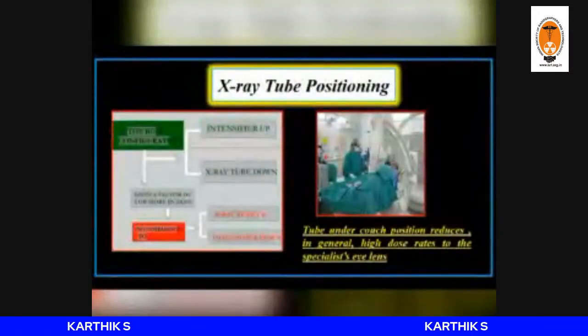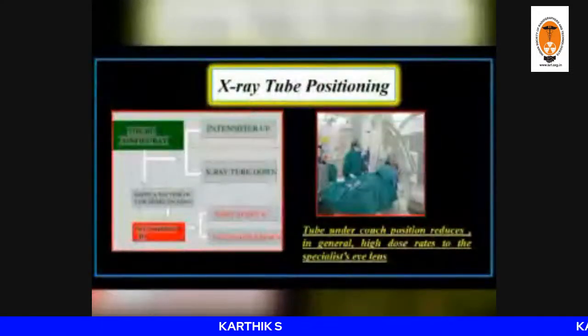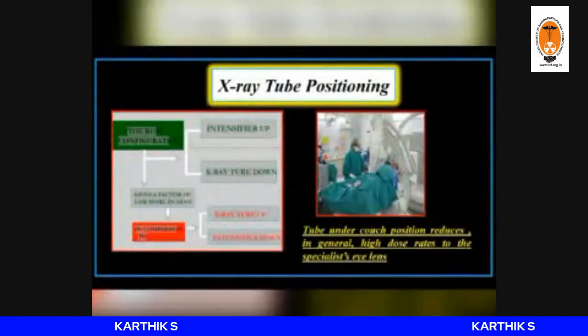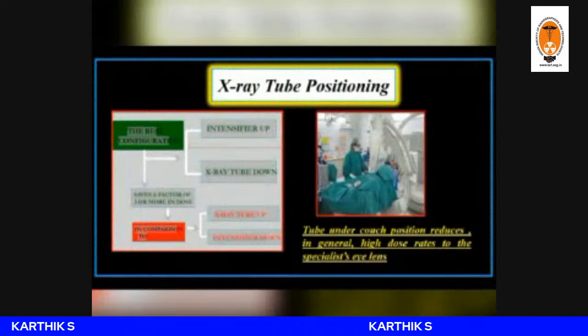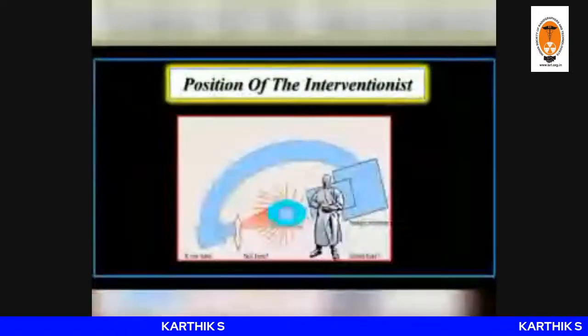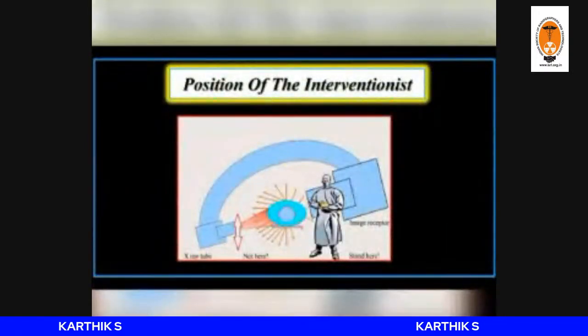X-ray tube positioning. The best configuration, image intensifier up and X-ray tube down, saves a factor of 3 or more in dose compared to X-ray tube up and image intensifier down. Position of the interventionist. In oblique projection, stand near the image receptor side, as exposure to the scattered radiation from the patient is reduced in this position.